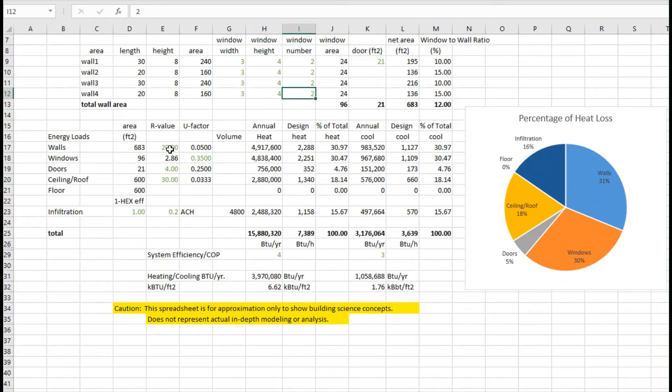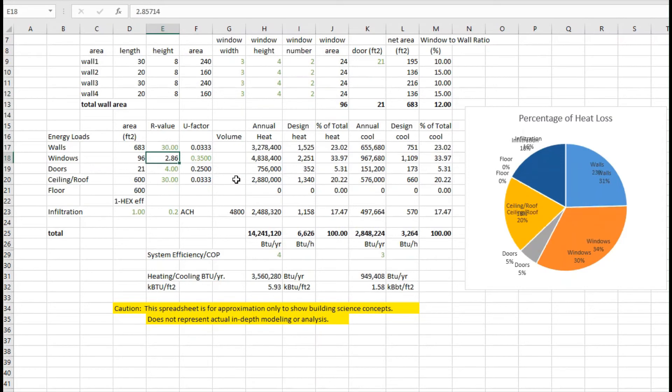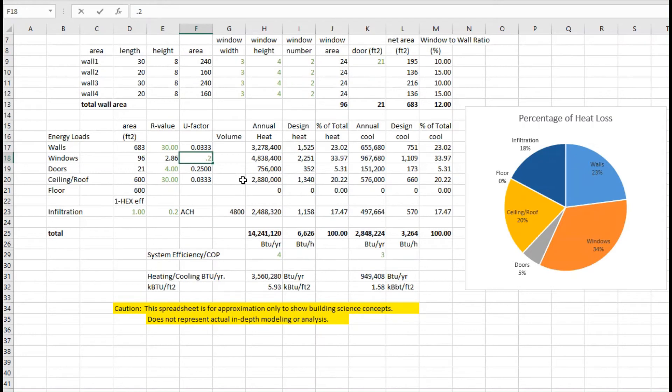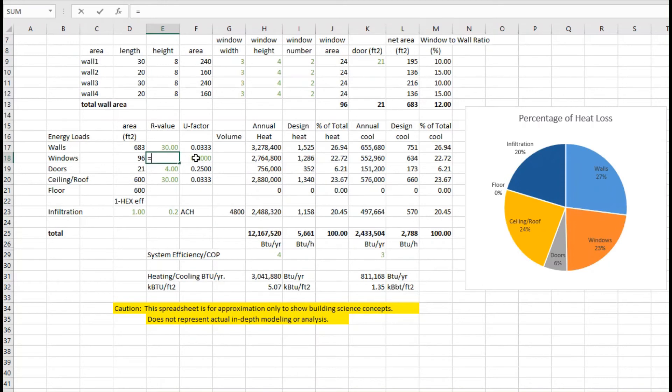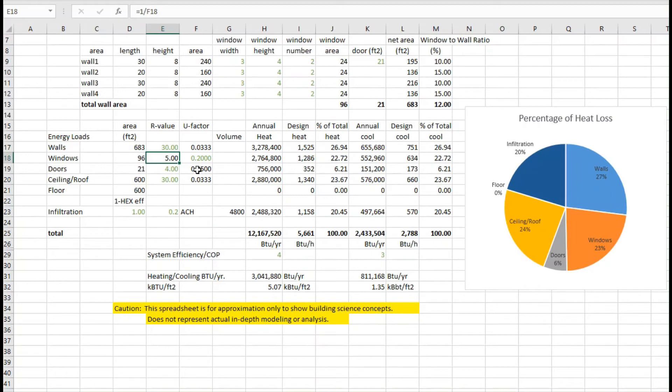Perhaps the walls, that seems to be pretty significant here. Maybe instead of R20, maybe we can move to an R30 wall. Maybe the windows, we're going to pick a better glazing, and maybe go to a U-factor - we'll be pretty aggressive here with a fancy window and go to 0.2 for that U-factor. I see here we actually have a calculation error. Let me just fix that while we're doing this. And so that becomes now R5 for the windows. So we've corrected that.